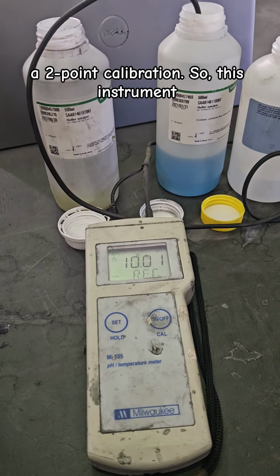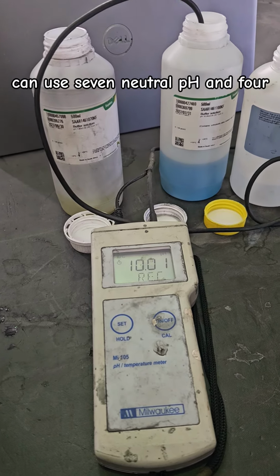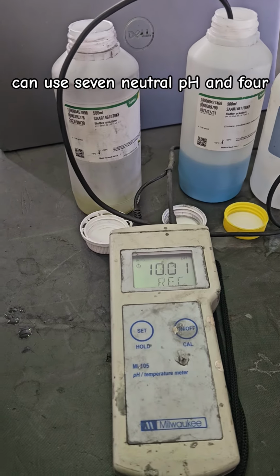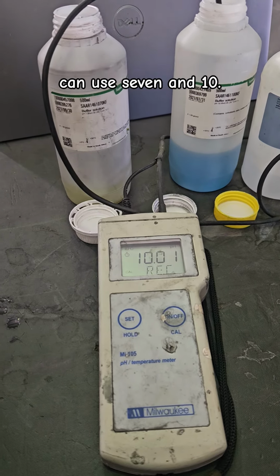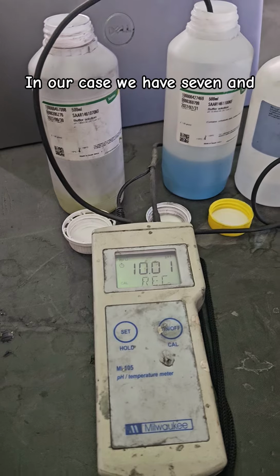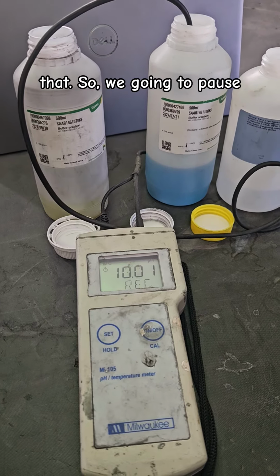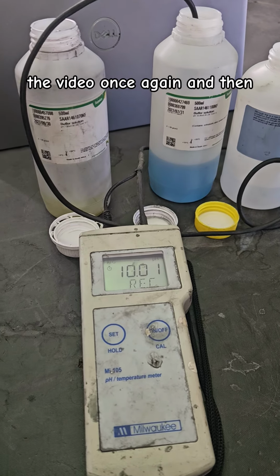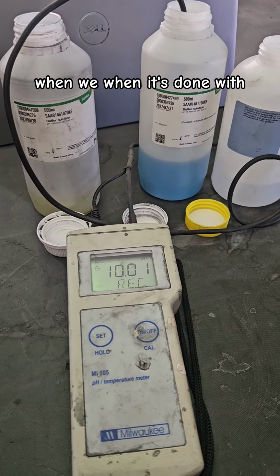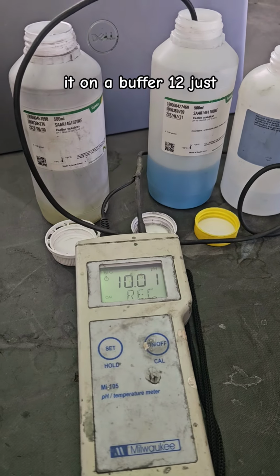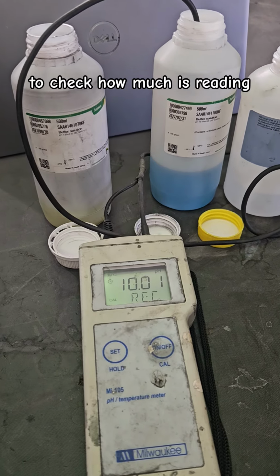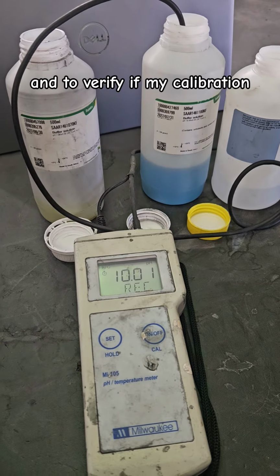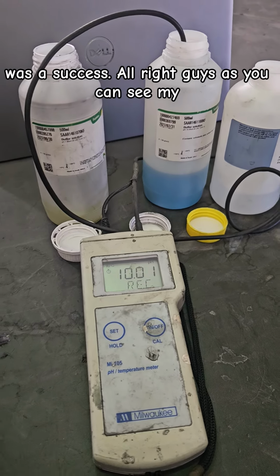So this instrument requires 2 points, which is, you can use 7 neutral and 4, which is more acidic, or you can use 7 and 10. In our case we have 7 and 10, so it's gonna use that. So we're gonna pause the video once again, and then when it's done with the calibration, I'm gonna put it on a buffer 10 just to check how much it's reading and to verify if my calibration was a success.